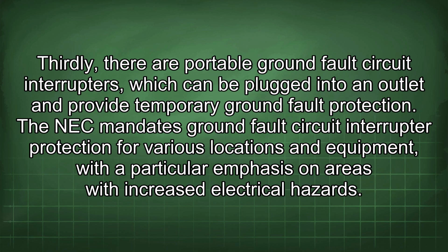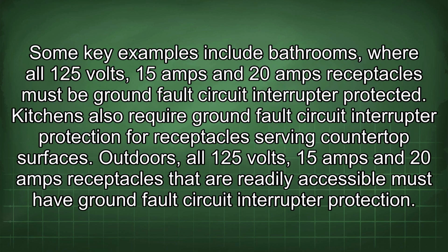The NEC mandates ground fault circuit interrupter protection for various locations and equipment, with a particular emphasis on areas with increased electrical hazards. Some key examples include bathrooms, where all 125 volt, 15 amp and 20 amp receptacles must be ground fault circuit interrupter protected. Kitchens also require ground fault circuit interrupter protection for receptacles serving countertop surfaces.